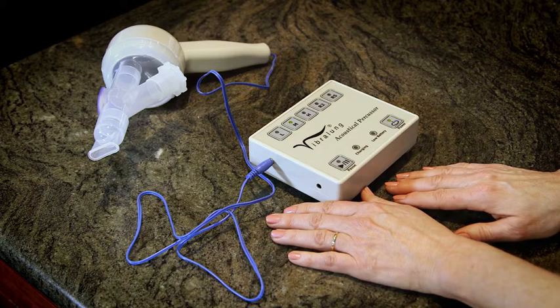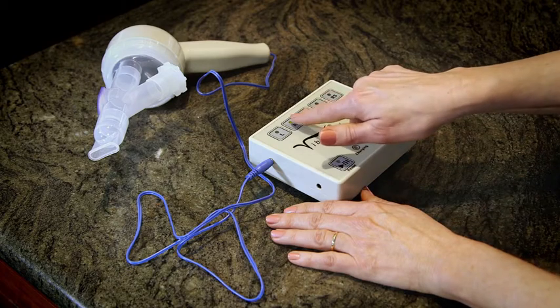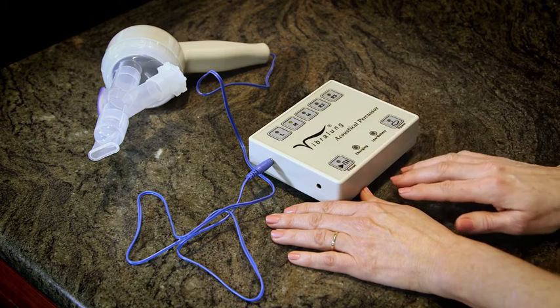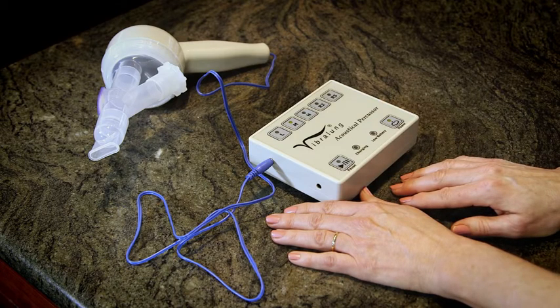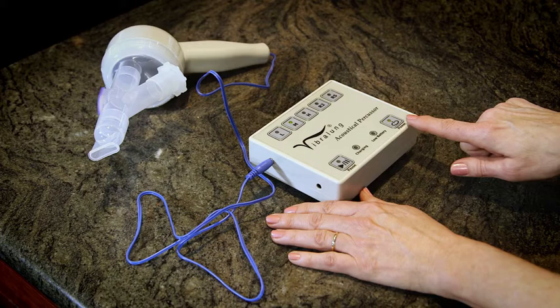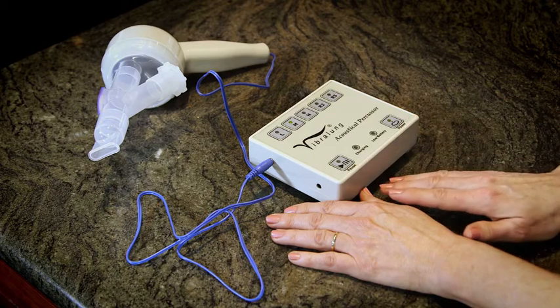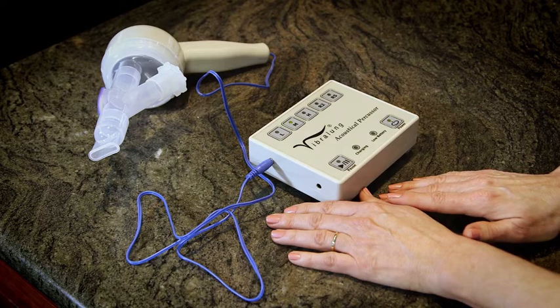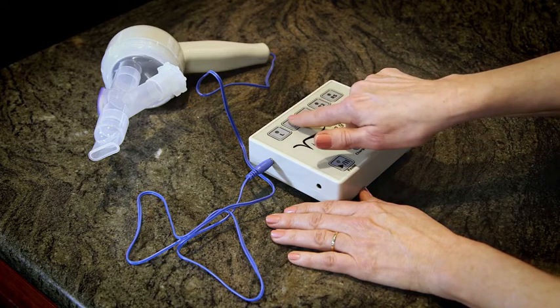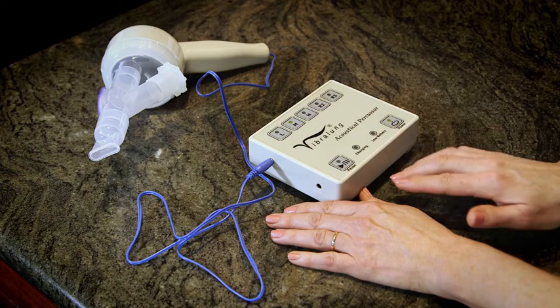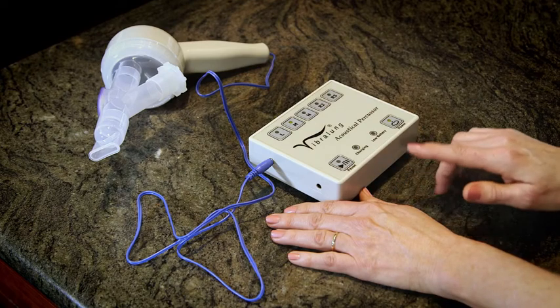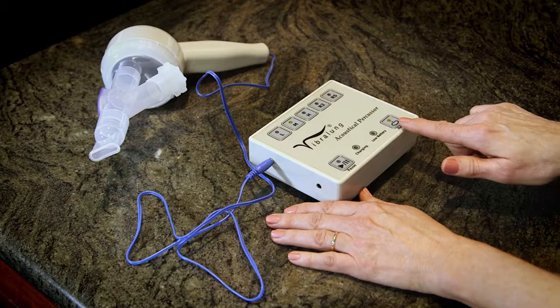If the patient perceives a point during treatment that feels especially beneficial, a treatment hold can be activated, where the 4-tone sound pattern of the patient's choosing will be played for 2 minutes. The treatment hold is activated by pressing and releasing the treatment button setting currently being used. The treatment hold is in effect as indicated by the blinking of the power button's LED. The treatment hold can be discontinued before the 2 minutes has expired by again pressing and releasing the currently selected treatment button setting. The power button's LED will then stop blinking. Treatment hold time is added to the total treatment time.